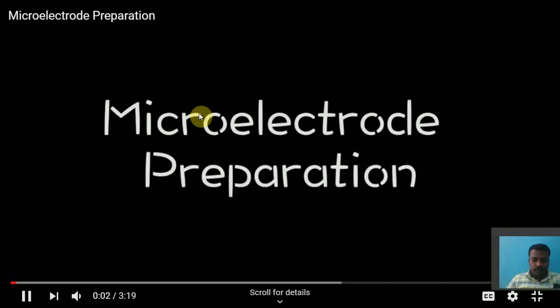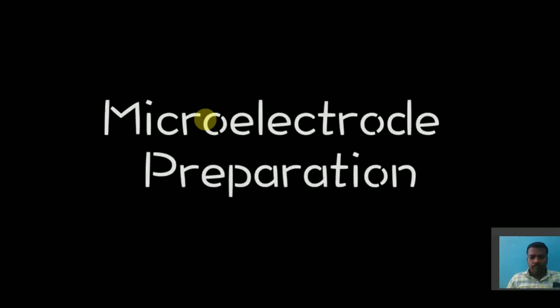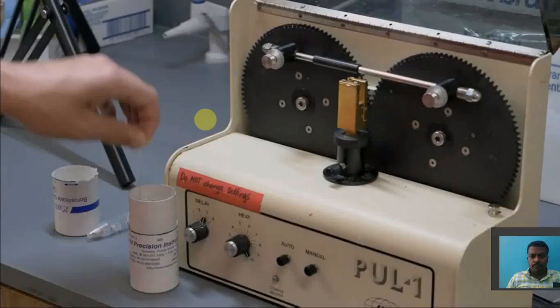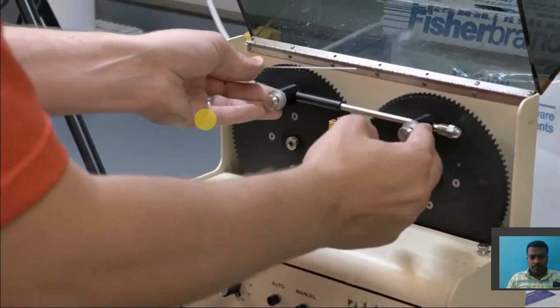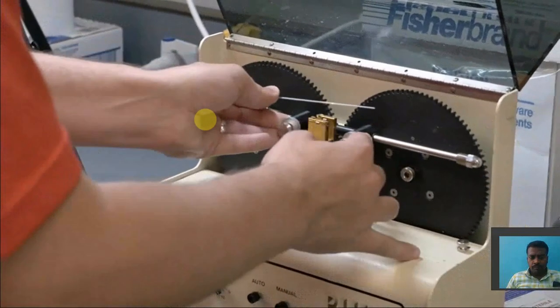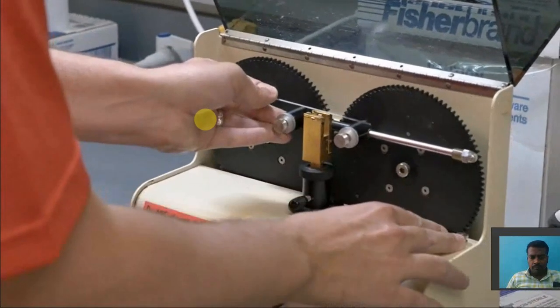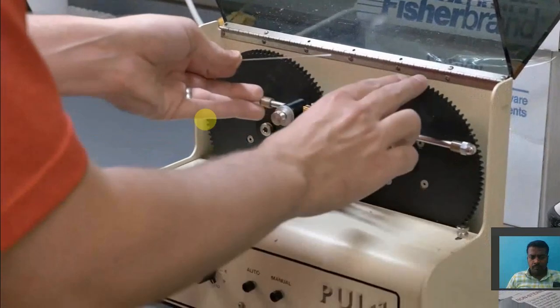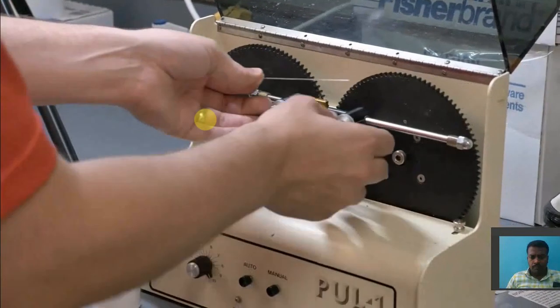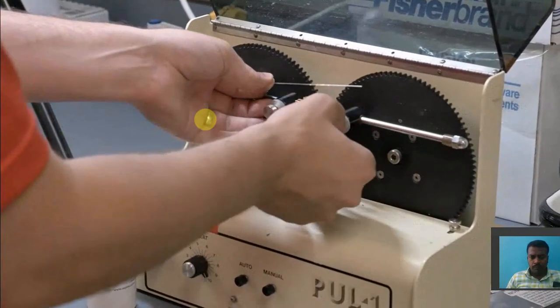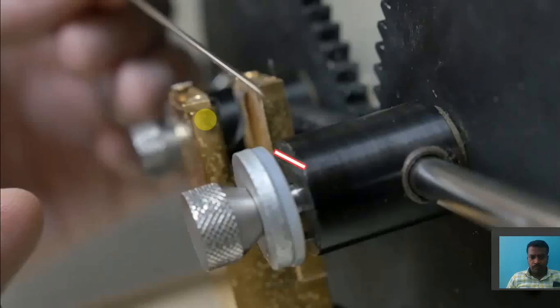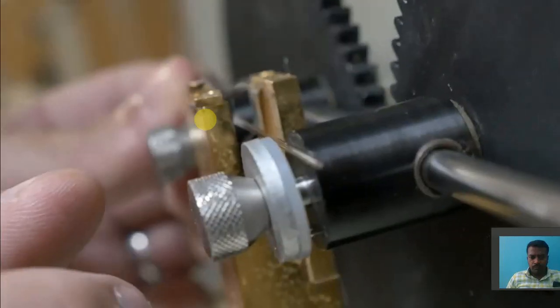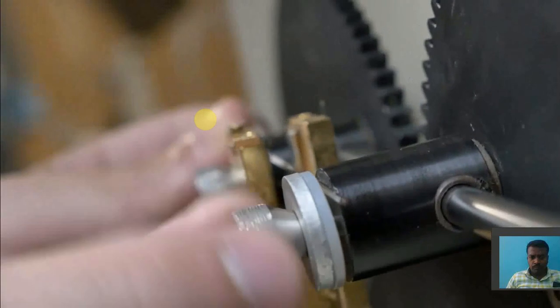Will instruct you on the preparation and care of an intracellular electrode and electrode holder. First, we will show you how to make an electrode. Take a capillary tube, push on the silver knobs to bring the wheels together, and set the brake. The brake is located in the lower right-hand corner. Make sure the knobs are loose, and then place the capillary tube in the slot shown here. Tighten the knobs to hold the capillary tube in place.